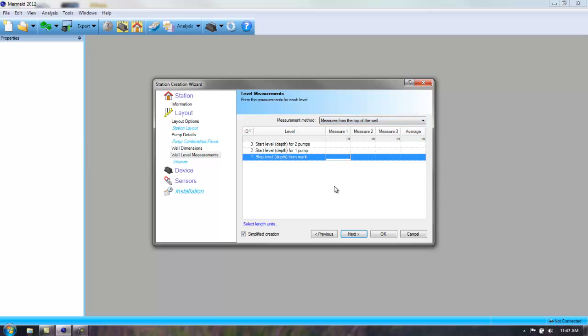And I'm going to say from the top of the well to the all-off point or stop level that it's 100 inches. Now my start level for pump 1 or my lead level is going to be 3 feet above my all-off point, which would be 64 inches. And then I'm going to say my lag point or my start level for the next pump would be 1 foot above it, which would be 52 inches. And then I press Next.